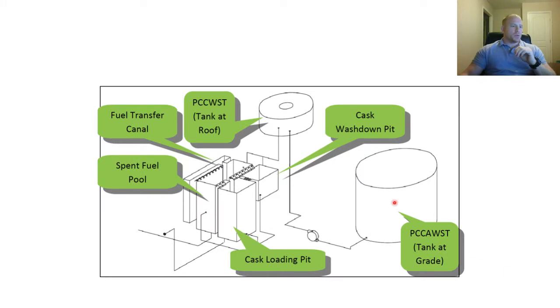Now the spent fuel pool. As we talked about earlier, the containment cooling water storage tank located at the top of the structure has a backup ancillary tank with a pump. This is an active safety system, but it is only necessary after the 3 days, and it will help provide makeup water to that tank, and that tank can provide cooling water to the spent fuel pool. The spent fuel pool has an initial volume inside it to keep the fuel pool cool for 3 days anyway, but after that point it will need more water from this tank and this tank. All right.